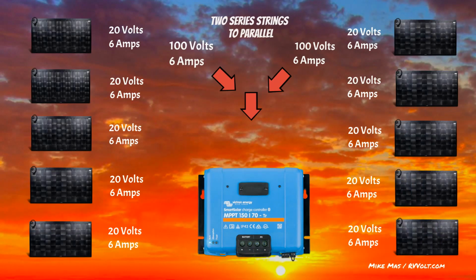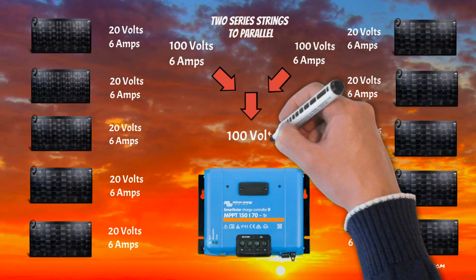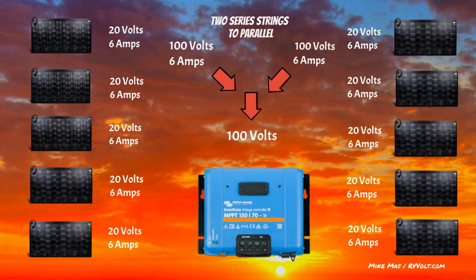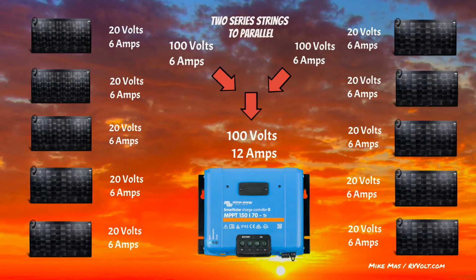Using a Y connector, we'll now join the outputs of both series strings in parallel to the Victron controller. Since these 2 sets are now in parallel, our voltage will remain the same at 100 volts. However, since this pair is now in parallel, our amperage will be added together for a total of 12 amps at 100 volts to our controller.